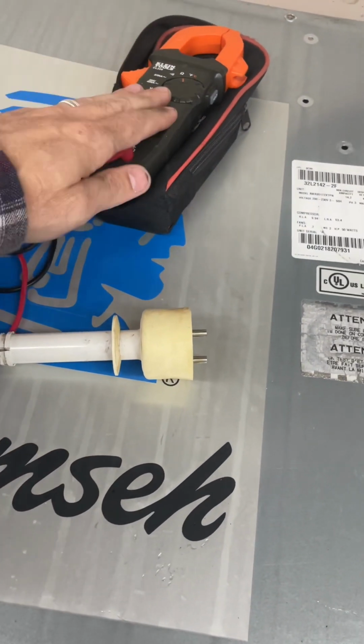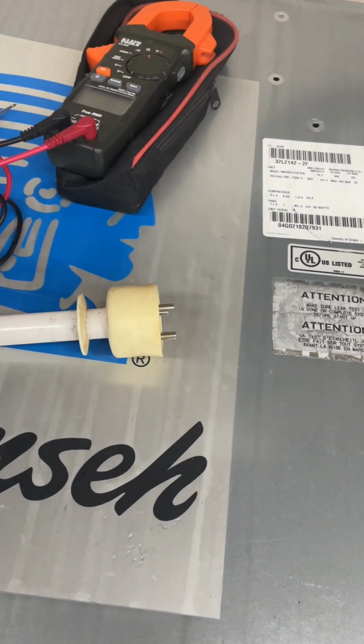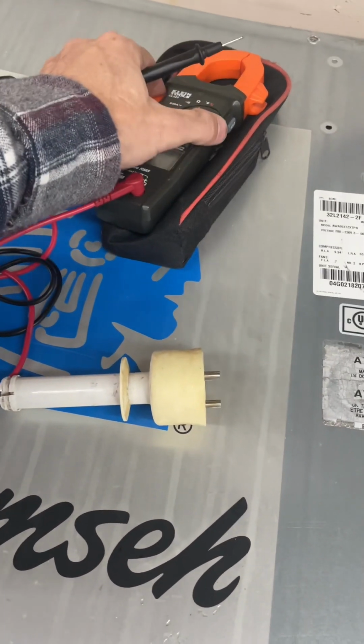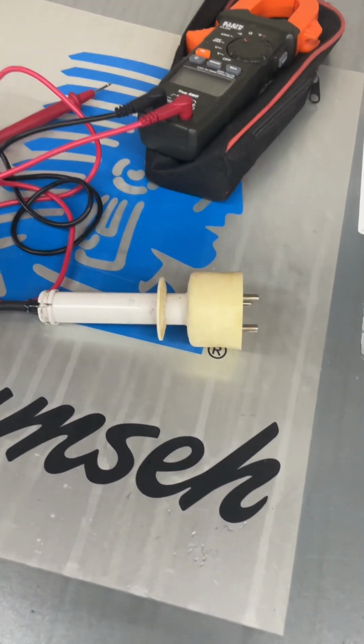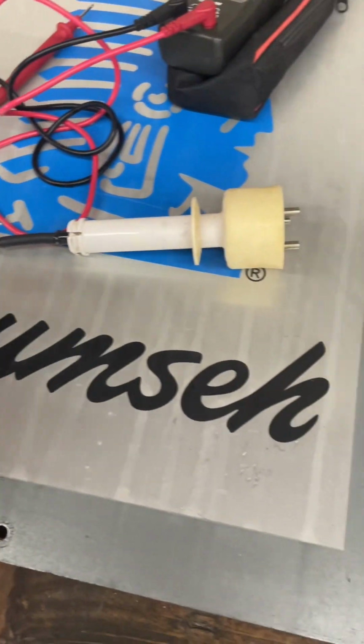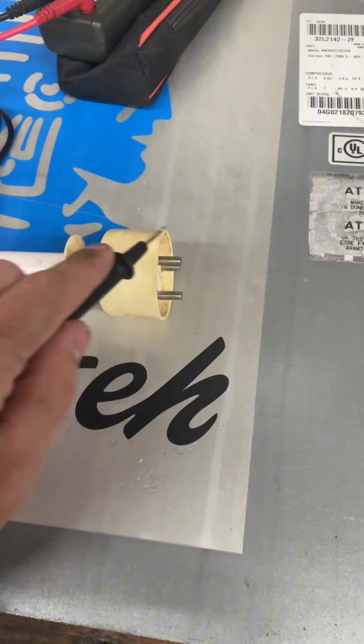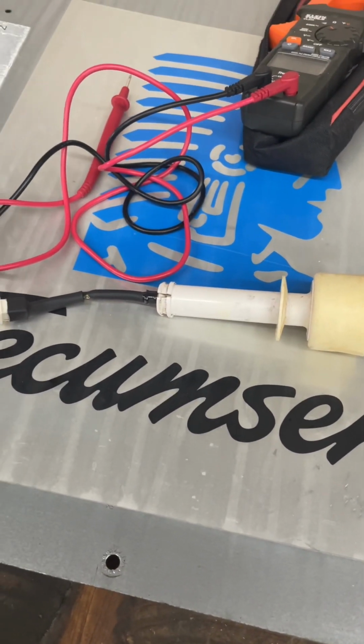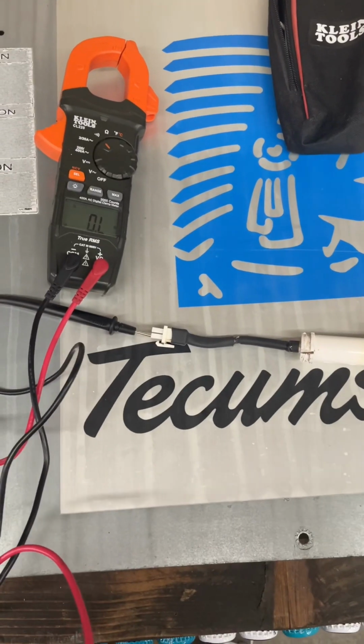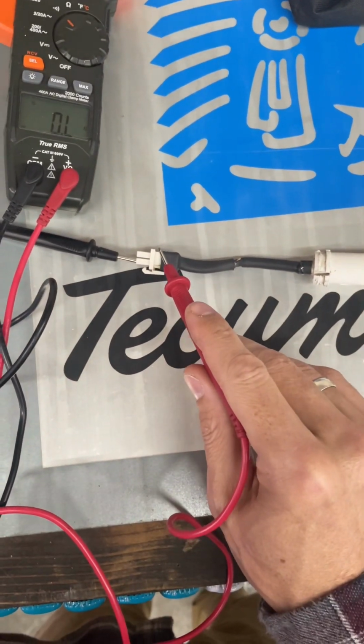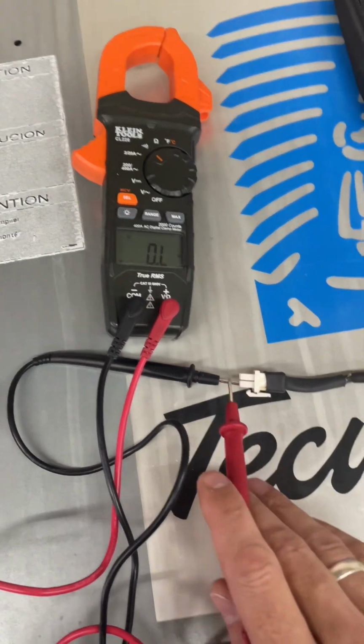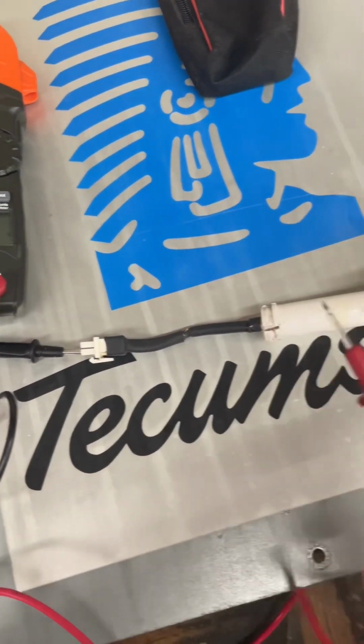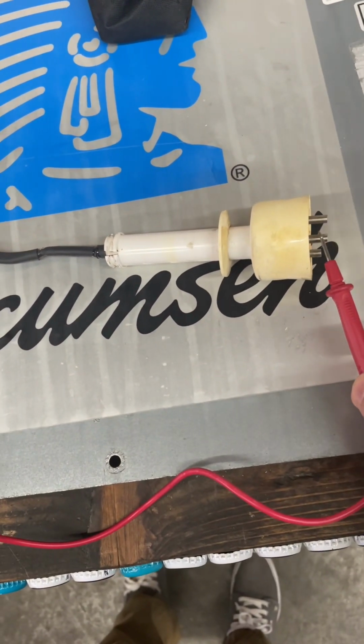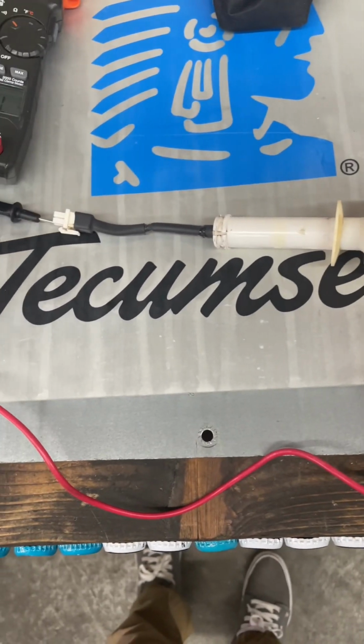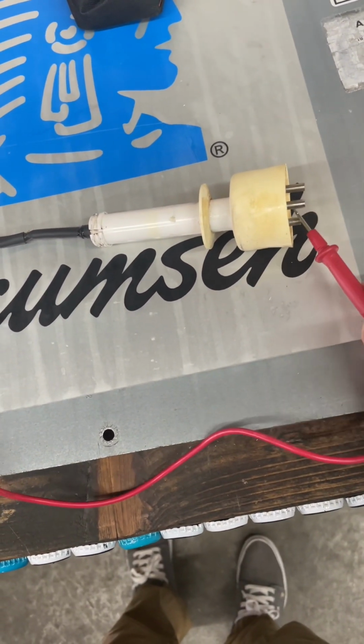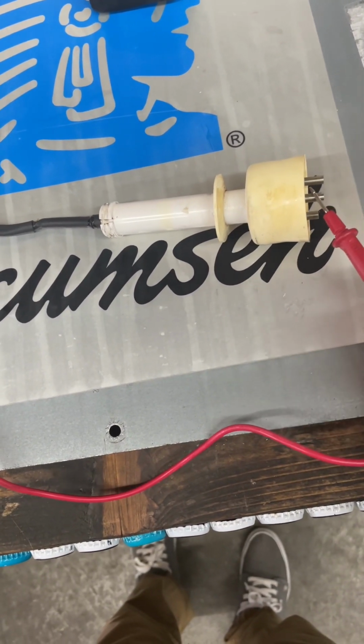Next, you're going to want to get a meter of some sort that you can test continuity with. Let me put it on the right setting. And then you should be able to get a tone between each one of these pins and each one of these prongs or probes, excuse me. So let me see if I can set this up and show it to you. All right, with one of my test leads inside of the plug and my meter set to check continuity on tone, we're gonna test by touching one of these probes, and it should give you a tone if there's continuity. And I'm not getting a tone on any of these.